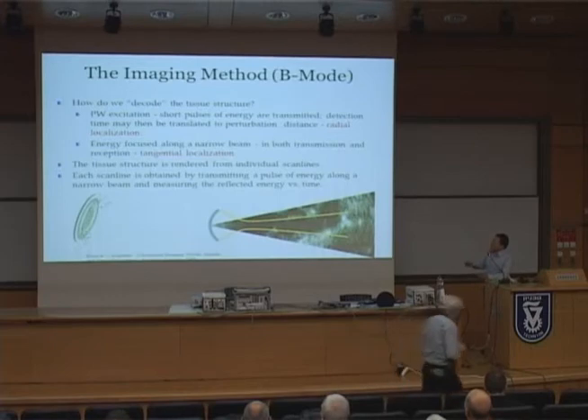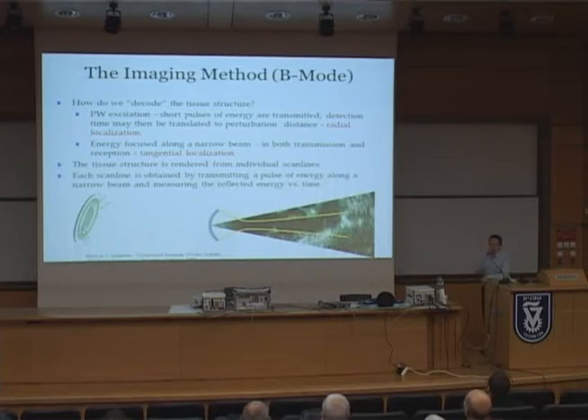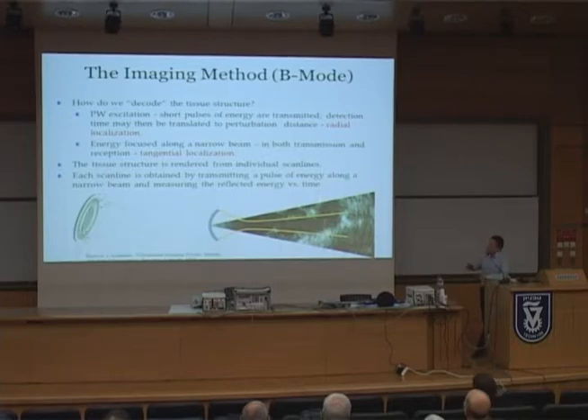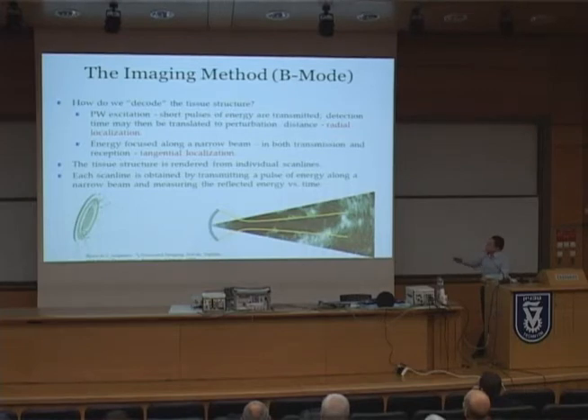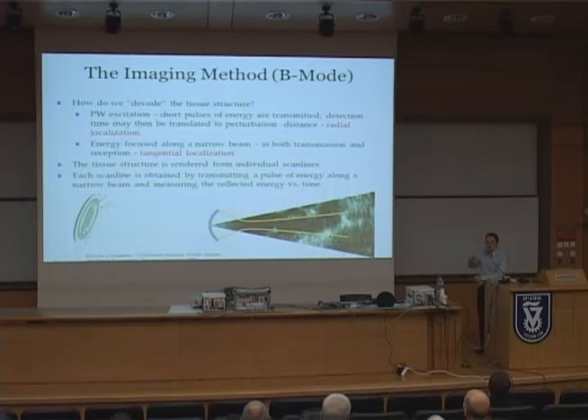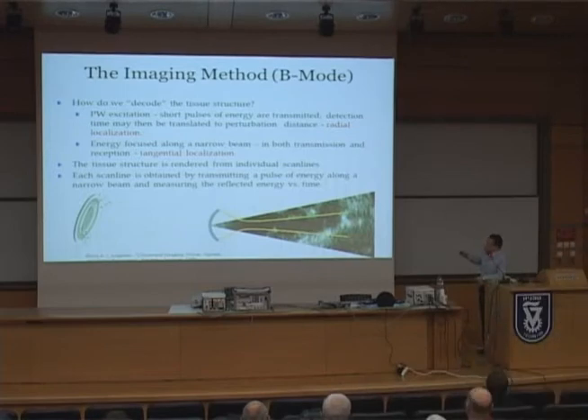An interesting question is how does a conventional ultrasound system recover the structure of tissue from reflected energy. This is quite similar to radar or sonar. By controlling the regime by which we transmit and detect energy, we can find a straightforward relationship between the reflected energy and the structure of the tissue. If the transducer transmits by pulse wave excitation — short pulses of energy — we get a straightforward relationship between the time we detect the echo and the distance to the perturbation causing that echo, giving us radial localization.